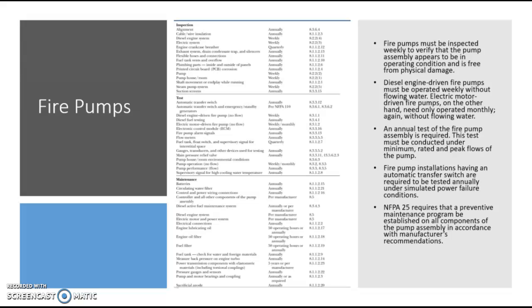which now brings us to fire pumps. Now, fire pump, this comes from NFPA naturally. It tells you what the inspections, the tests, the maintenance are covering. This is actually in the write-up that we've sent in. The fire pumps have to be inspected weekly to verify that the pump assembly appears to be operating. There's no physical damage. A lot of fire pumps have an automatic testing mode, and that's usually done by the owner, either early in the morning or late at night.